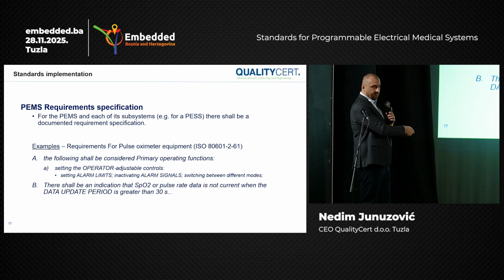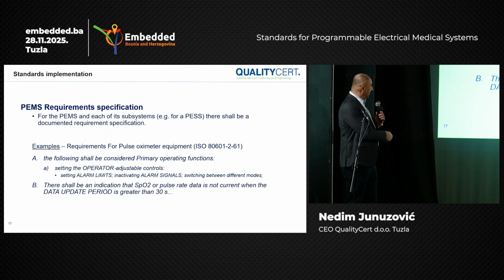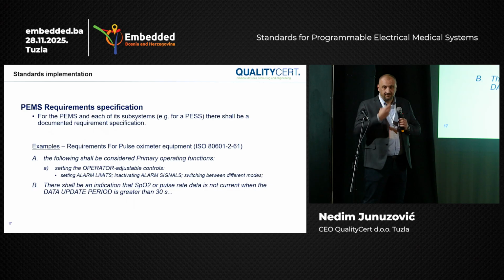The other one has some measurable points, which says: there shall be indication that SpO2 or pulse rate data is not current when the data update period is greater than 30 seconds.